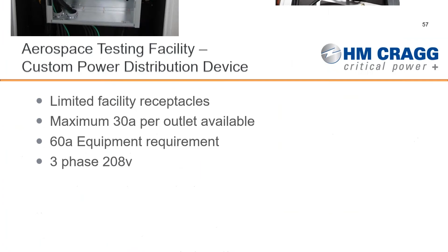Okay, yeah, this is another opportunity that we had for a custom unit. This is where I start to put on my PDU hat a little bit. We had an aerospace testing facility who was not allowed to change any of the facility wiring in the space they were in. They had 3-phase 208 30 amp circuits available, and they had a piece of equipment that required a 60 amp draw. So myself and Kevin, the applications engineer, worked to design a device that will do just that.